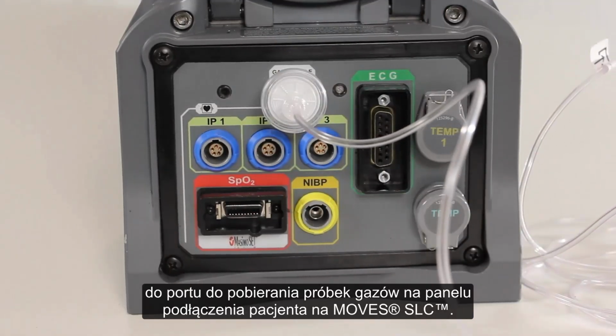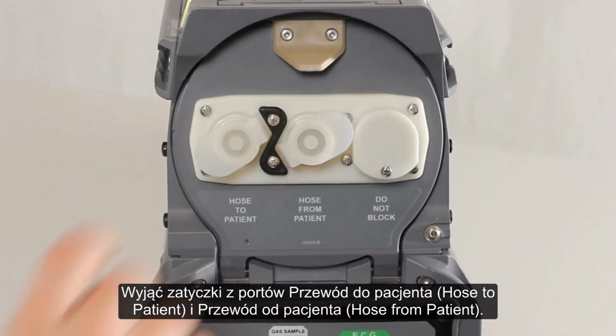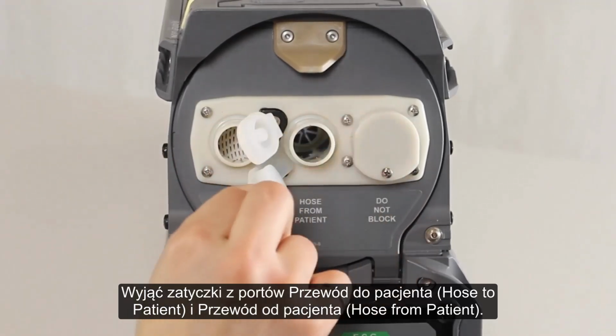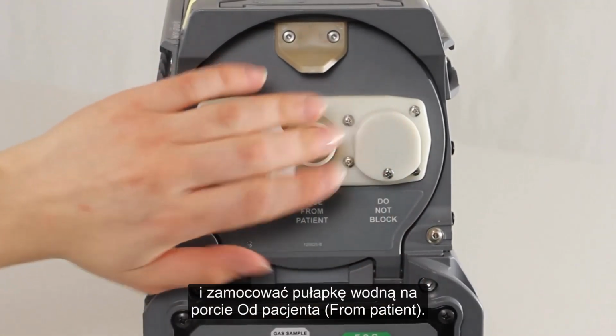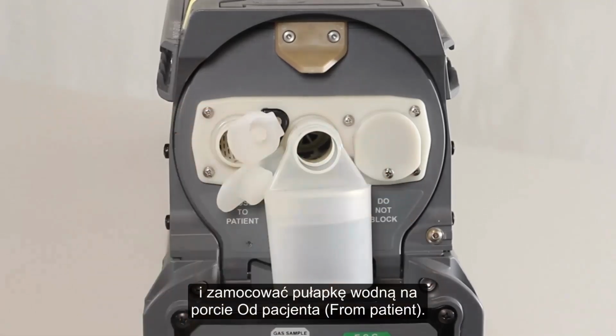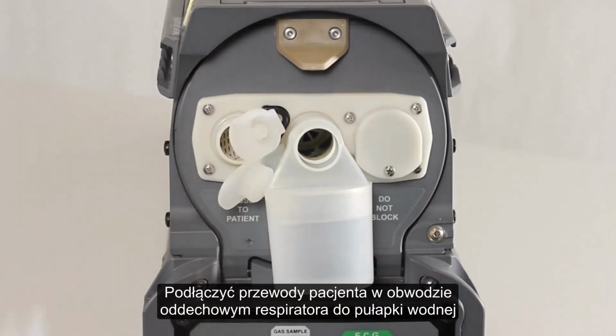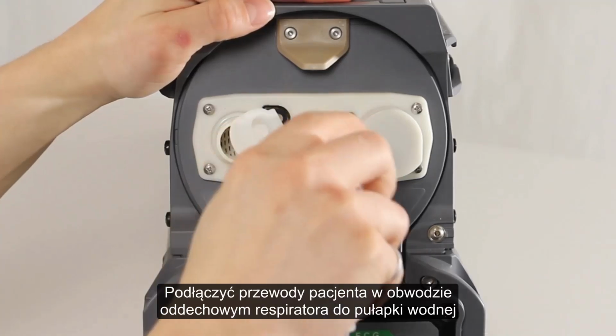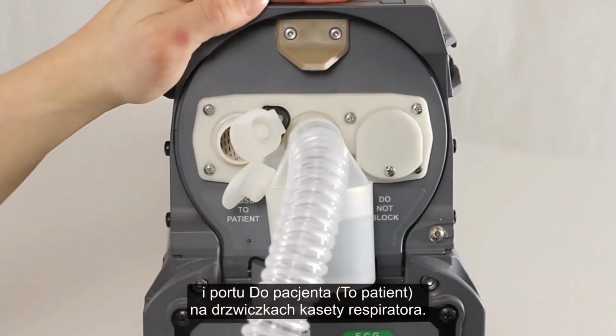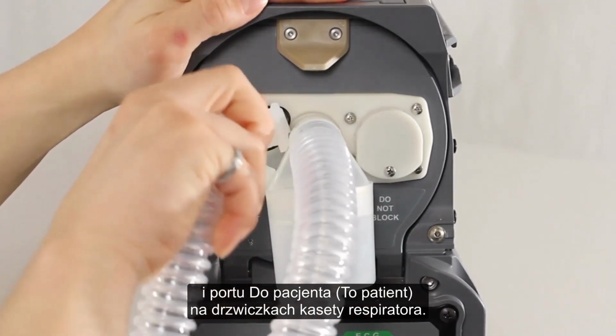SLC Patient Connections panel. Unplug the hose covers on the hose to patient and hose from patient ports and attach the water trap to the From Patient port. Attach the ventilator breathing circuit patient hoses to the water trap and the To Patient port on the ventilator cartridge door.